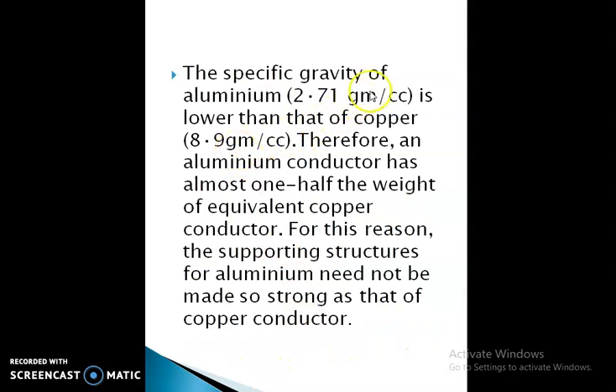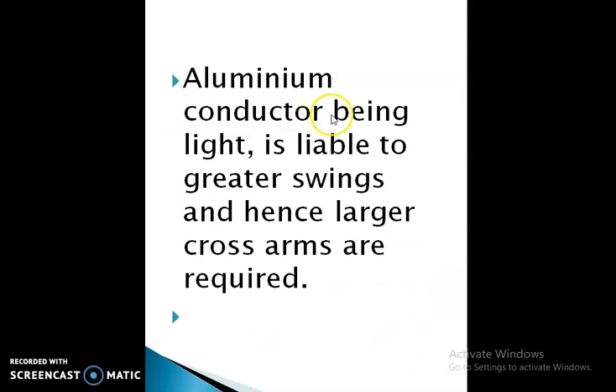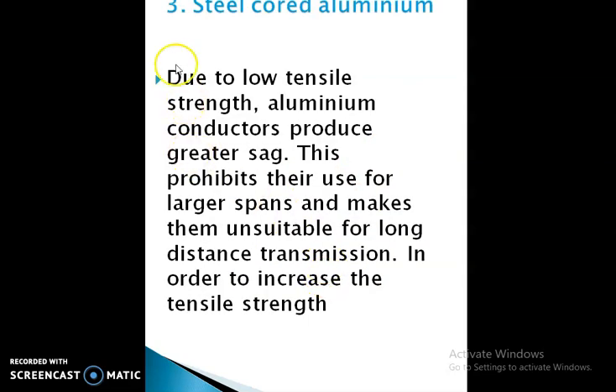The specific gravity of aluminum is 2.71 g/cc, which is lower than that of copper at 8.9 g/cc. Therefore, an aluminum conductor has almost one half the weight of an equivalent copper conductor. For this reason, supporting structures for aluminum need not be made as strong as those for copper conductors. However, the aluminum conductor being light is liable to greater swing, and hence larger cross arms are required.